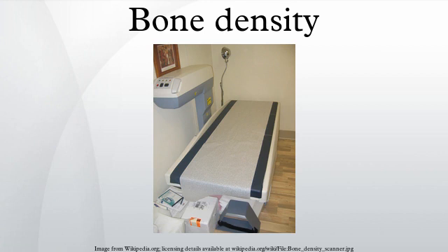Measurement can be affected by the size of the patient, the thickness of tissue overlying the bone, and other factors extraneous to the bones. Bone density is a proxy measurement for bone strength, which is the resistance to fracture and a truly significant characteristic. Although the two are usually related, there are some circumstances in which bone density is a poorer indicator of bone strength. Reference standards for some populations are unavailable for many of the methods used. Crushed vertebrae can result in falsely high bone density, so must be excluded from analysis.